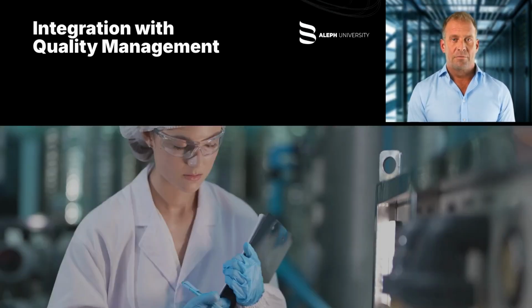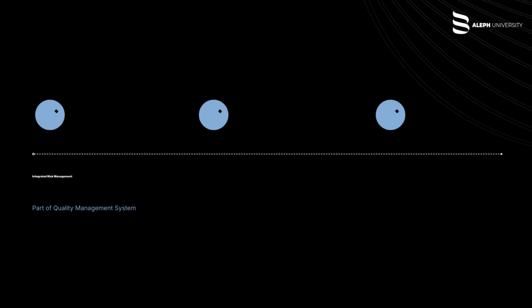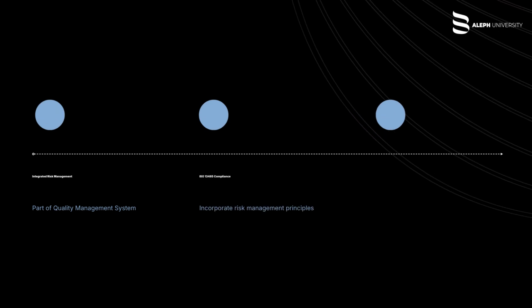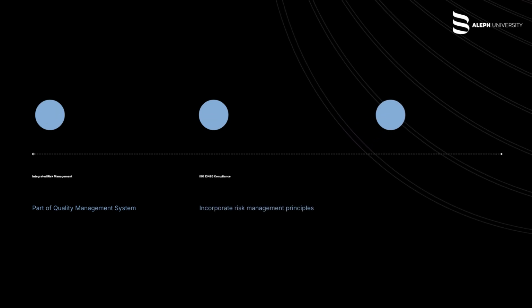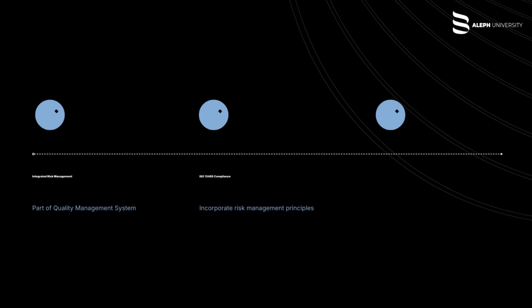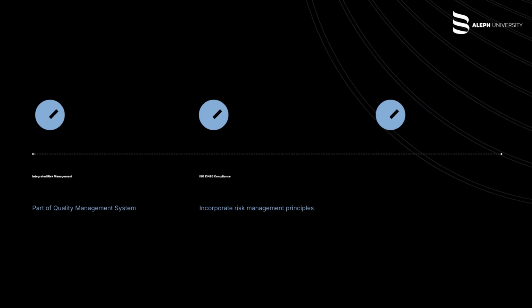Integration with quality management systems. Risk management is not a standalone process, but should be integrated into the organization's overall quality management system, QMS. ISO 13485, the standard for medical device quality management systems, requires manufacturers to incorporate risk management principles into their processes. This integration ensures that risk management activities are embedded in design and development, production, and post-market activities, fostering a culture of continuous improvement and proactive hazard mitigation.